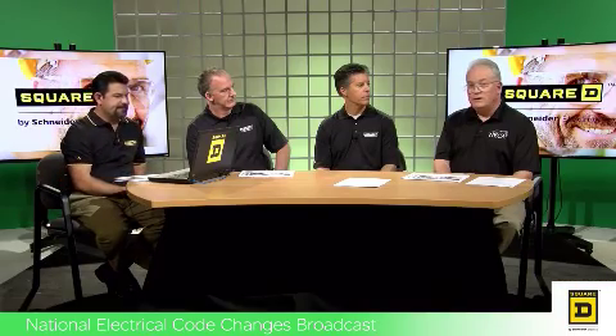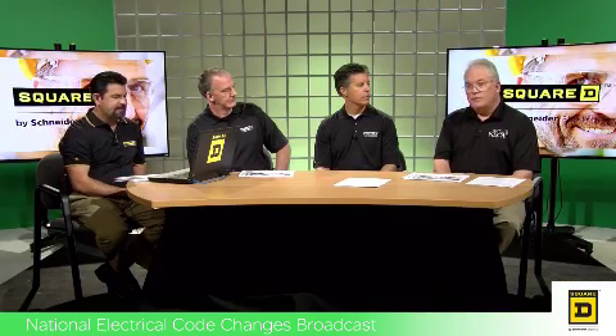This is the section of the code that actually acts as an exception to Table 310.15(B)(16), your normal ampacity values. You're allowed to take a 0.83 reduction factor from the values in Table 310.15(B)(16) and apply those to services and main power feeders for dwellings at the 100 amp level through 400 amp level single phase. So the big change in this section allows one to take a single phase feeder from a 208Y/120 fed service and supply the main power feeders or the service itself. So an expansion within that section.